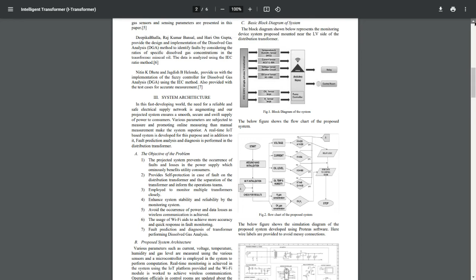The block diagram represents the proposed monitoring device system. Various parameters such as current, voltage, temperature, humidity, and gas levels are measured using various sensors, and a microcontroller is employed to perform computation. Real-time monitoring is achieved using the IoT platform, and the Wi-Fi module is used to achieve wireless communication. Based on the occurrence of a fault, depending on predefined instructions, the relay employed in the system gets activated and protects the transformer. The gas sensors employed perform dissolved gas analysis and predict the occurrence of incipient faults using a fuzzy controller designed based on the various gas concentrations.